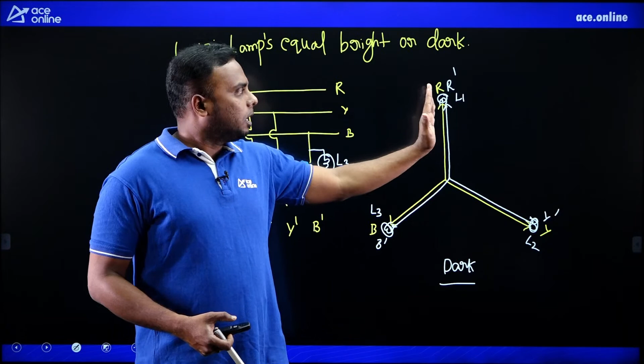Whenever you get this condition, equal bright or equal dark, only one should occur, not both. You may get equal bright continuously or equal dark continuously. Suppose you observe for 1 minute dark only, 2 minutes dark only, even 1 hour dark only, that means they are exactly in phase. Or if you get bright, that means they are out of phase. If you get bright position for 2 minutes and the same brightness continues after 30 minutes, it means they have same frequency, same sequence, but are out of phase.